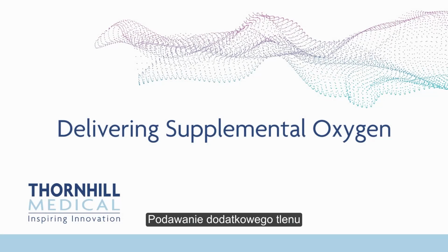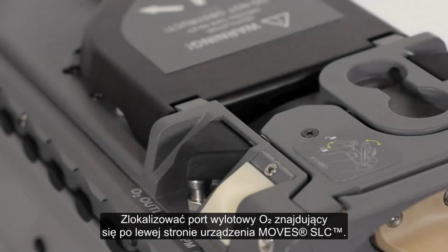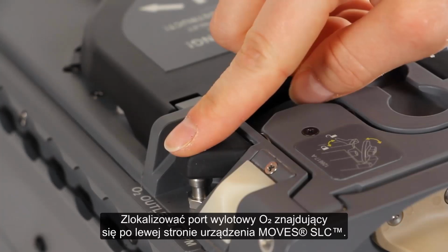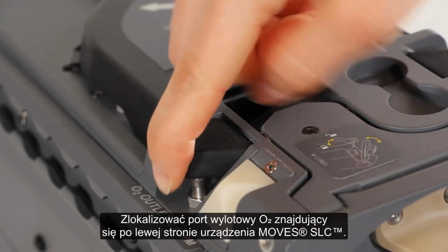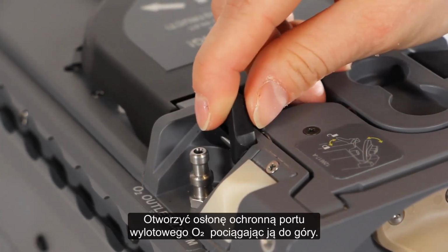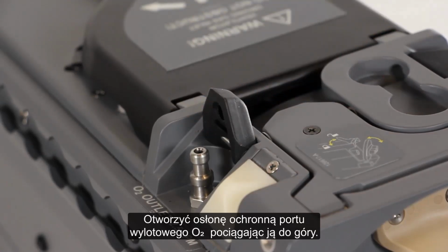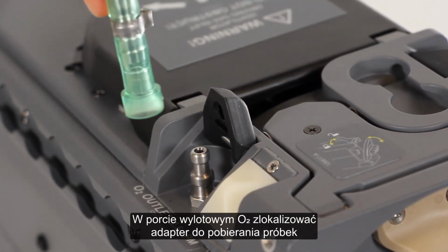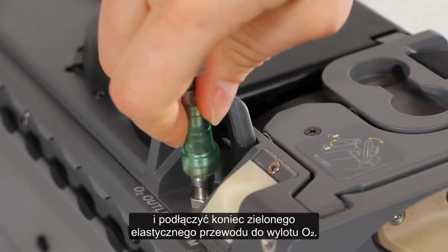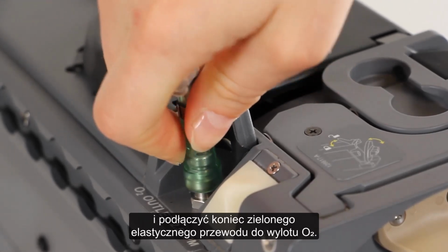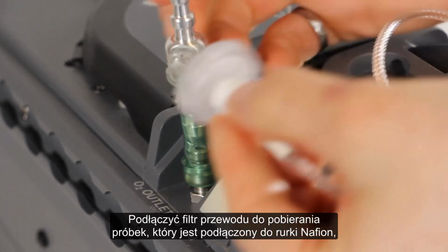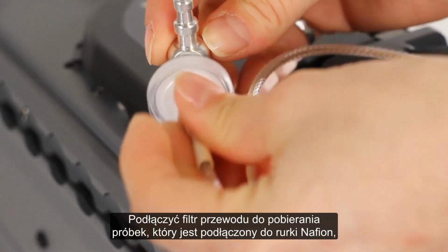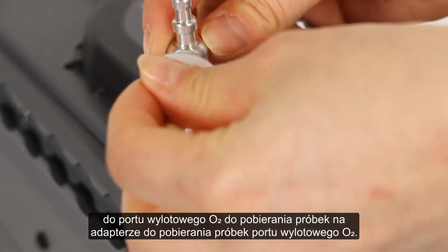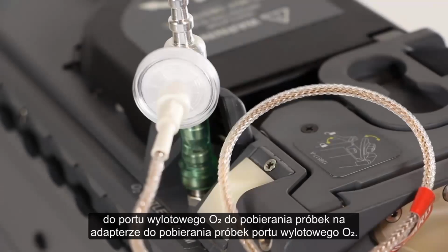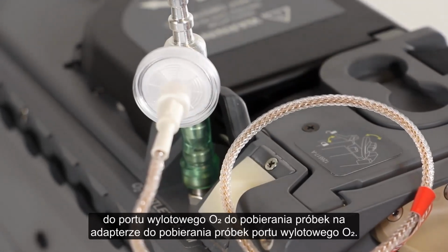Delivering supplemental oxygen. Locate the O2 outlet port located on the left side of the Moves SLC. Open the protective cover of the O2 outlet port by pulling it up. Locate the O2 outlet sampling adapter and connect the green flexible tubing end to the O2 outlet. Attach the sample line filter that is connected to the Nafion tube to the O2 outlet sampling port located on the O2 outlet sampling adapter.